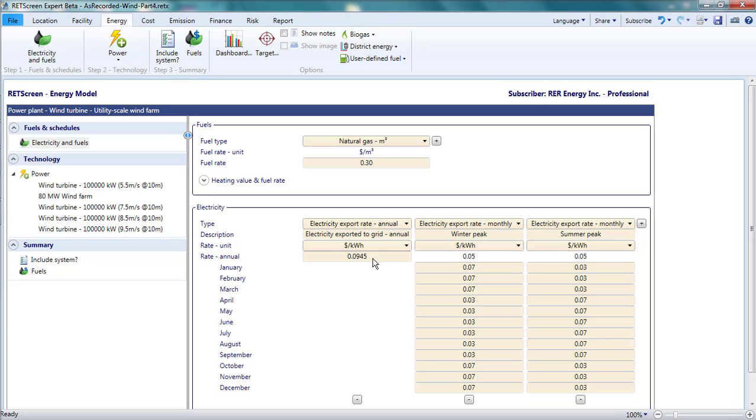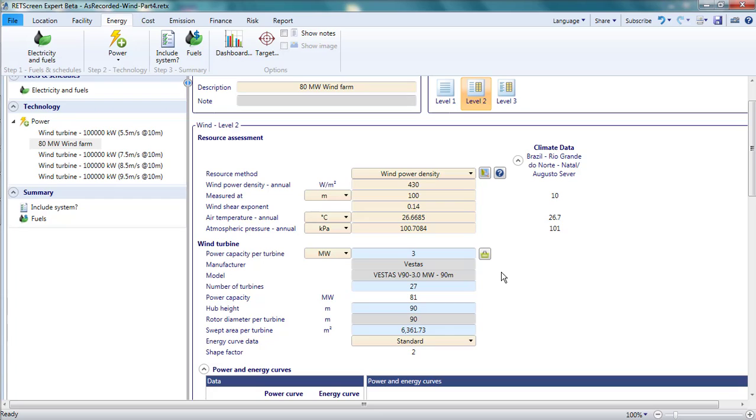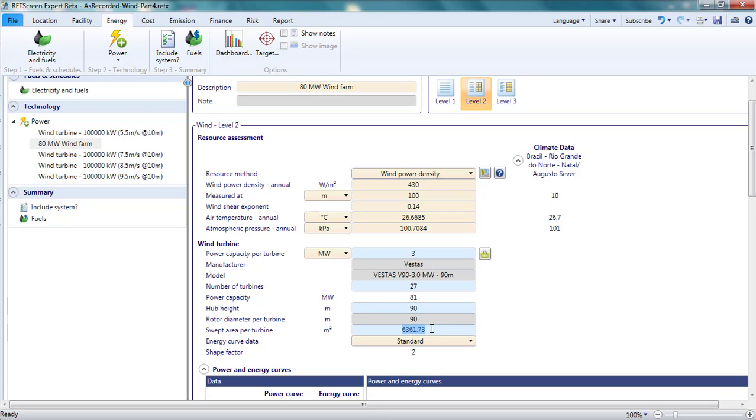Fortunately, the wind industry has done a lot to improve turbine performance in modest and low wind speed regimes. The first tactic is to use longer rotor blades, or smaller drivetrains for a given rotor size. The second is to use taller towers. Regardless of the rated power of the drivetrain, the input power that a turbine has to work with is related to the swept area of the rotor. If the wind resource is weak, longer blades will increase the input power and raise the capacity factor, assuming the generator is kept the same.